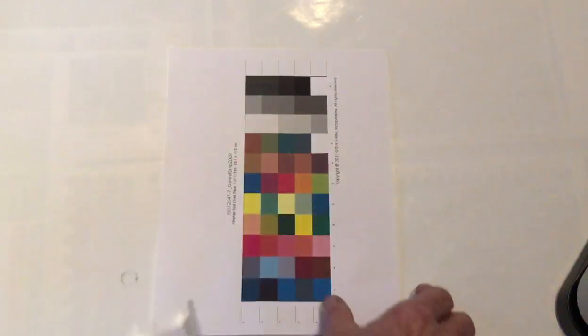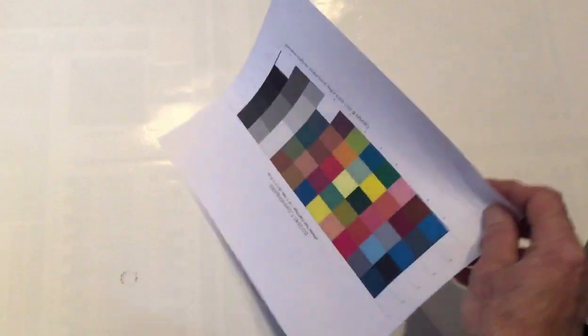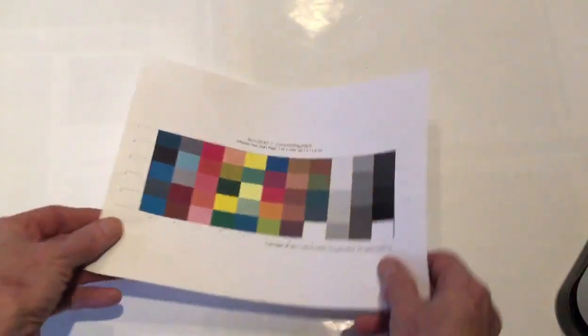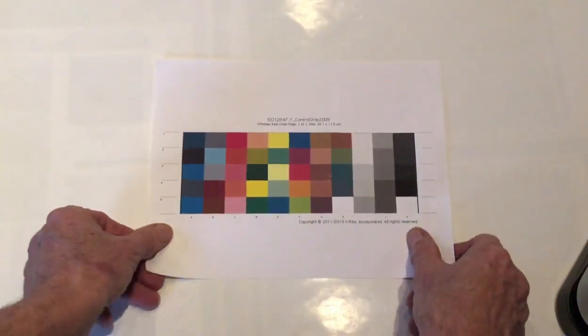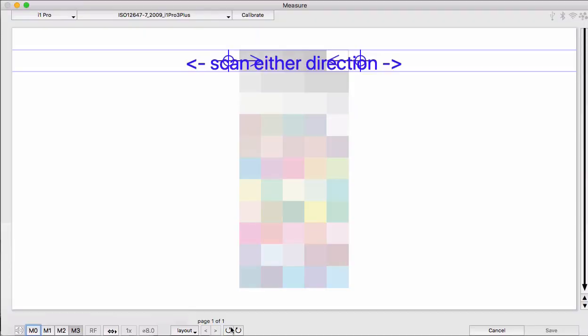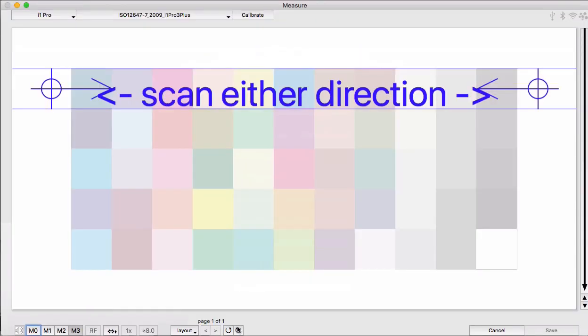For example, say you could have a vertical P2P target and a target reference, but you know it would measure more quickly if you could measure it horizontally, and this will allow you to do that. We'll do something similar with this 54-patch target.